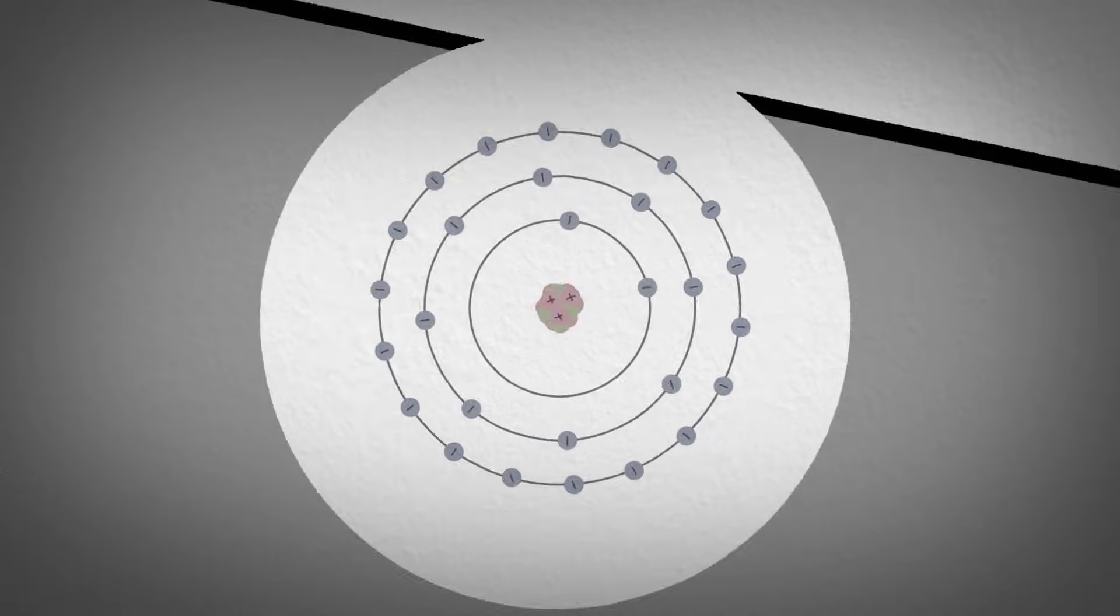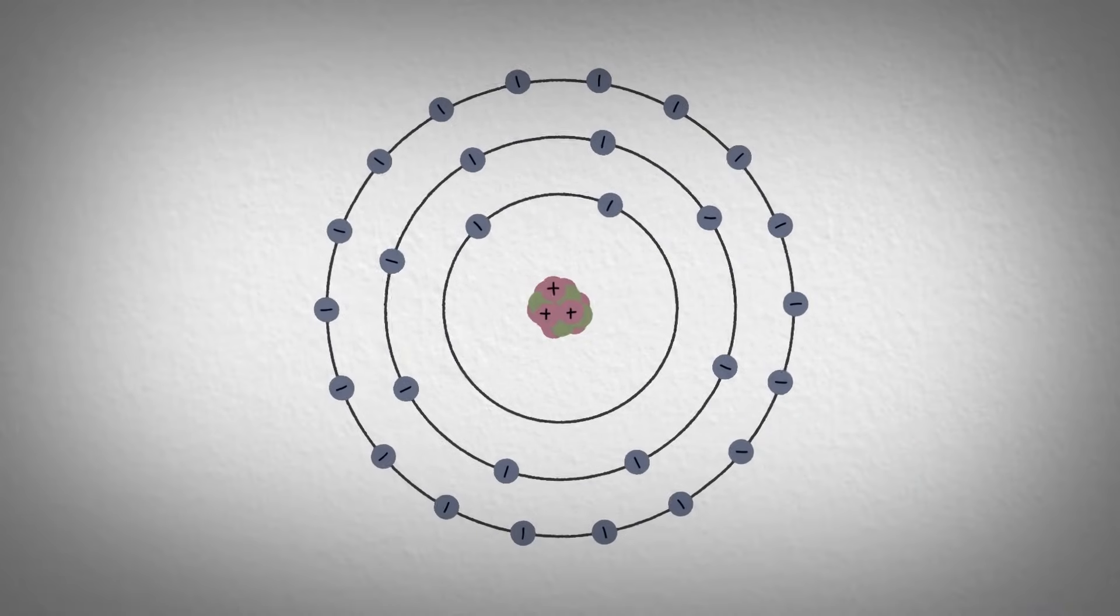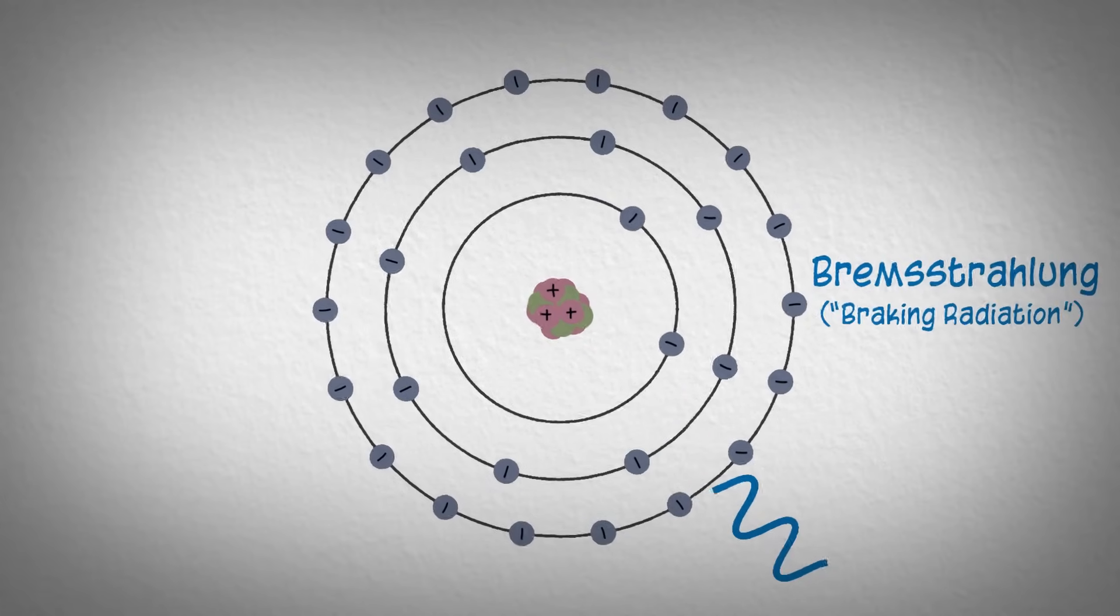When the electrons interact with the atoms in the anode, two different things can occur. The first possibility is that the electron will change speed and direction due to the atom's nucleus, producing a broad emission spectrum known as bremsstrahlung, German for braking radiation.